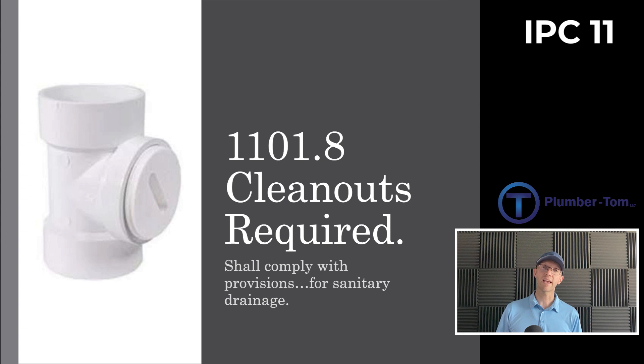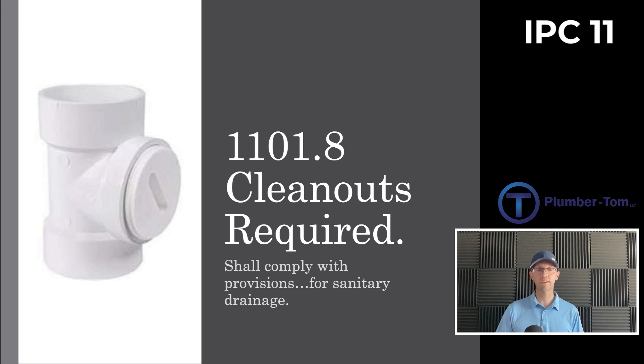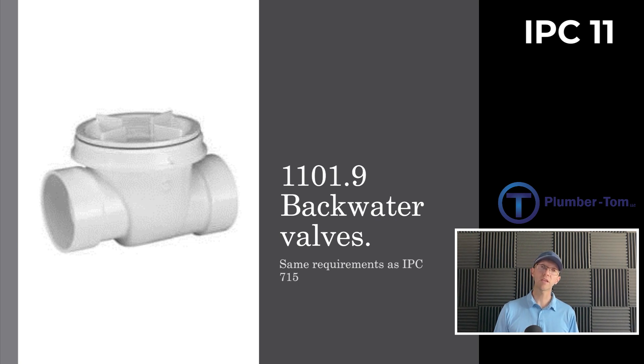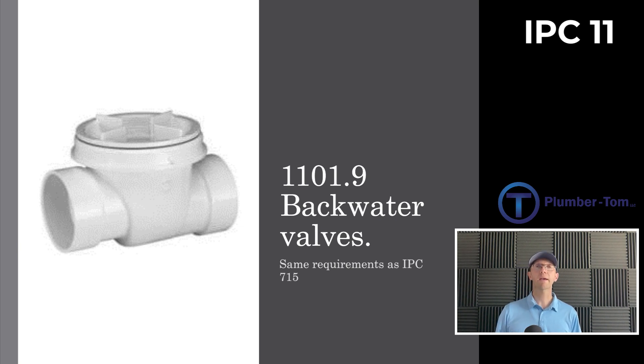1101.8 states that cleanouts will be installed with these drains similar to any others — it shall comply with the provisions for sanitary drainage cleanouts. The same rules from Chapter 7 about when and where to have cleanouts apply equally to storm drainage. Similarly, 1101.9 notes that there may be situations where backwater valves are used in a storm drainage setting, referring us back to Section 715 for all requirements on backwater valves.